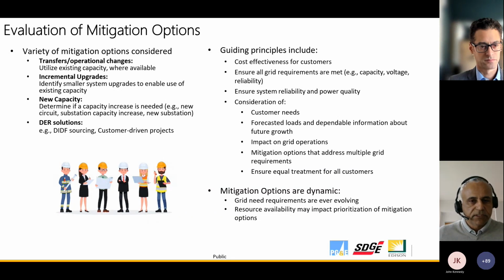We also look at small incremental upgrades that allow us to use the capacity — for example, a voltage issue that can be solved by installing a voltage device, which is much cheaper than replacing existing facilities. Then there are cases where we don't have enough substation capacity. We need to determine: do we install a new circuit, add or replace a transformer at the substation to increase capacity, or in some cases build a new substation? We need to look at all of that.